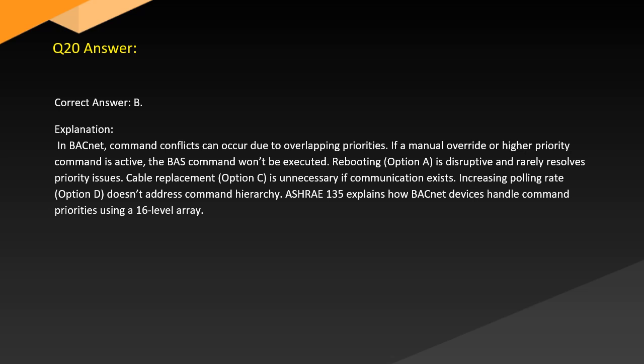If a manual override or higher priority command is active, the BAS command won't be executed. Rebooting, option A, is disruptive and rarely resolves priority issues. Cable replacement, option C, is unnecessary if communication exists. Increasing polling rate, option D, doesn't address command hierarchy. ASHRAE 135 explains how BACnet devices handle command priorities using a 16-level array.